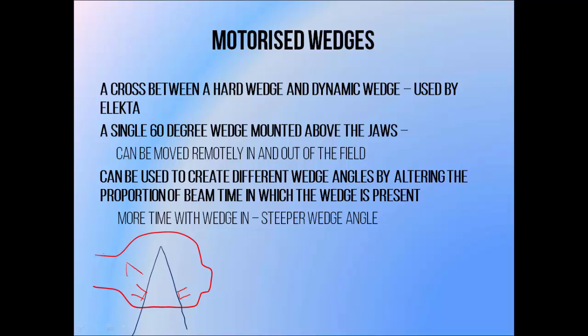Elekta uses a motorized wedge. It's a large-angle hard wedge that sits inside the linac treatment head just above the secondary collimator jaws. It can be moved remotely in and out of the beam at will. The actual physical wedge only has one angle — about 60 degrees, which is the largest you'd normally see in clinical practice. But this can be used to create different wedge angles by delivering part of the beam without the wedge in the beam, and part of the beam with the wedge in the beam.